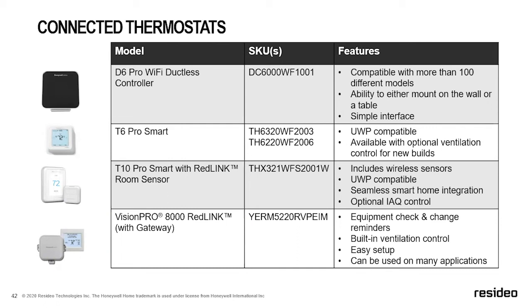What I mean by that is, let's say during the day, the thermostat's on the first floor, we are going to run the schedule to control that at the thermostat. And then at night, we could start looking at the sensor, which might be in the master bedroom. We either average the two or just have that remote sensor take over as the control point. And it's also got an optional IAQ control, so I can hook up a humidifier, dehumidifier, or ventilator right to this T10. Again, it works on the universal wall plate.